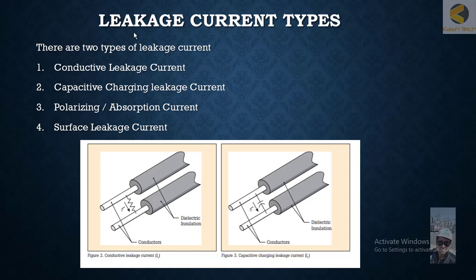In this section we will discuss the types of leakage current. As seen previously, leakage current depends on insulation resistance and is the sum of four different currents: the conductive leakage current, the capacitive charging leakage current, the polarizing absorption current, and the surface leakage current. The sum of all four forms the total leakage current.